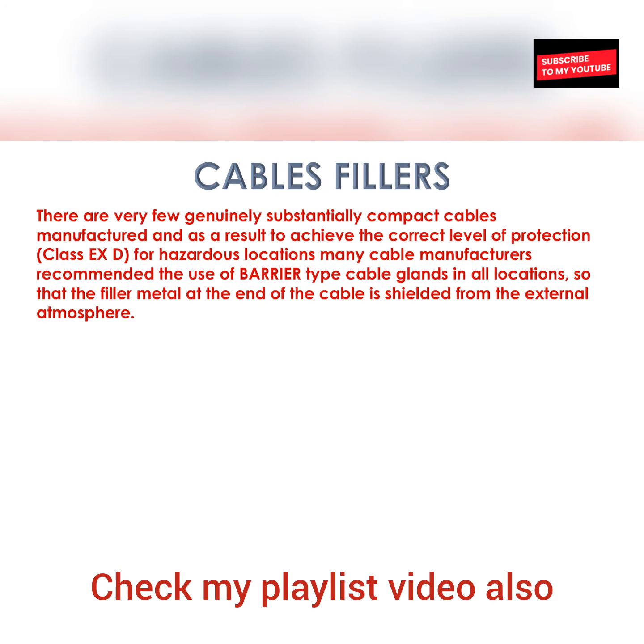There are very few genuinely substantial compact cables manufactured, and as a result, to achieve the correct level of protection, Class Ex d hazardous locations recommend the use of barrier-type cable glands in all locations, so the filler at the end of the cable is shielded from the external atmosphere.